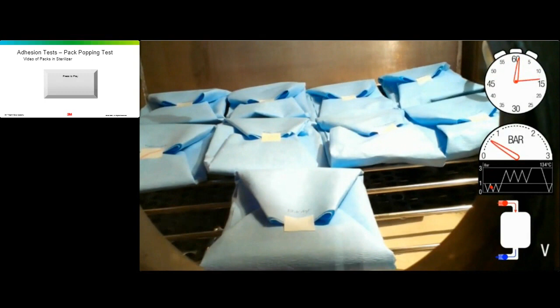You can see that already in that right-hand side, one of the packs has already popped open. We're now blowing steam into the chamber, and then we're evacuating it again. And again, as a result of those pressure changes, one of the packs has popped open. And now we're starting to draw a vacuum. And that particular tape has given way at this point in the cycle. We're now pressurizing the chamber again with steam, and then we will evacuate, and you can see those packs ballooning, and some of the tapes are not able to hold that force which the ballooning creates. Again, we're going through a sequence of evacuation and steam admission.